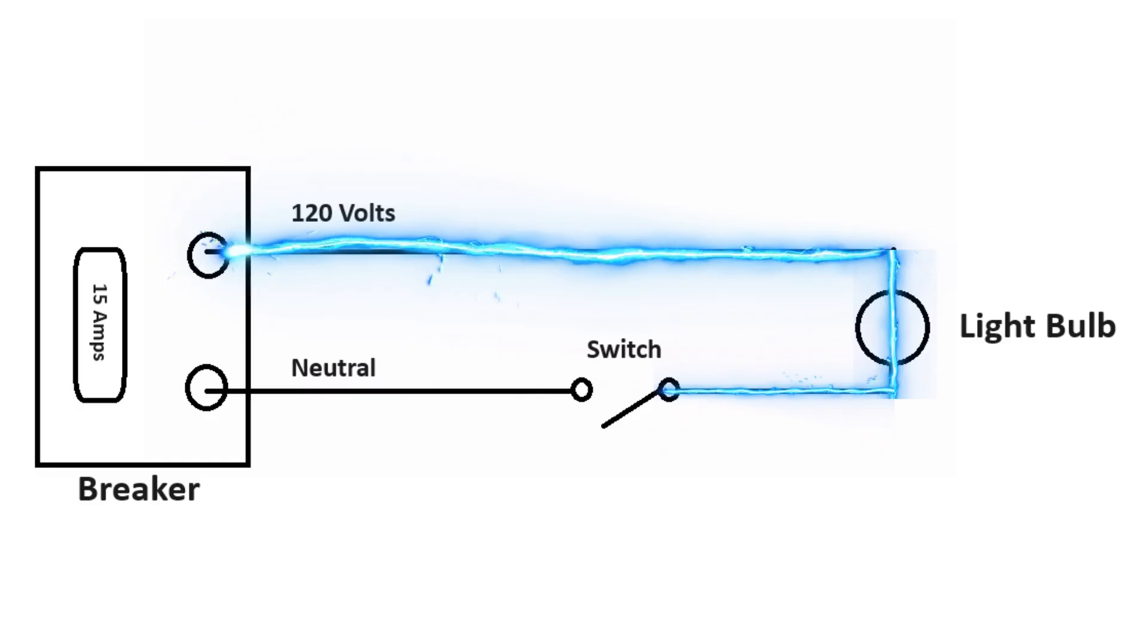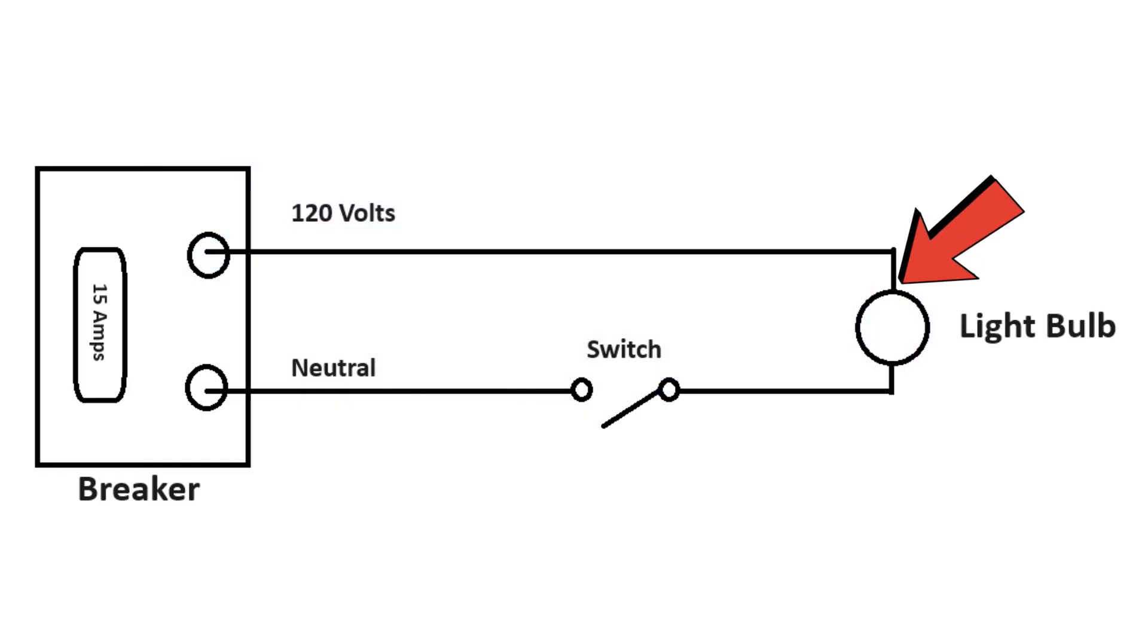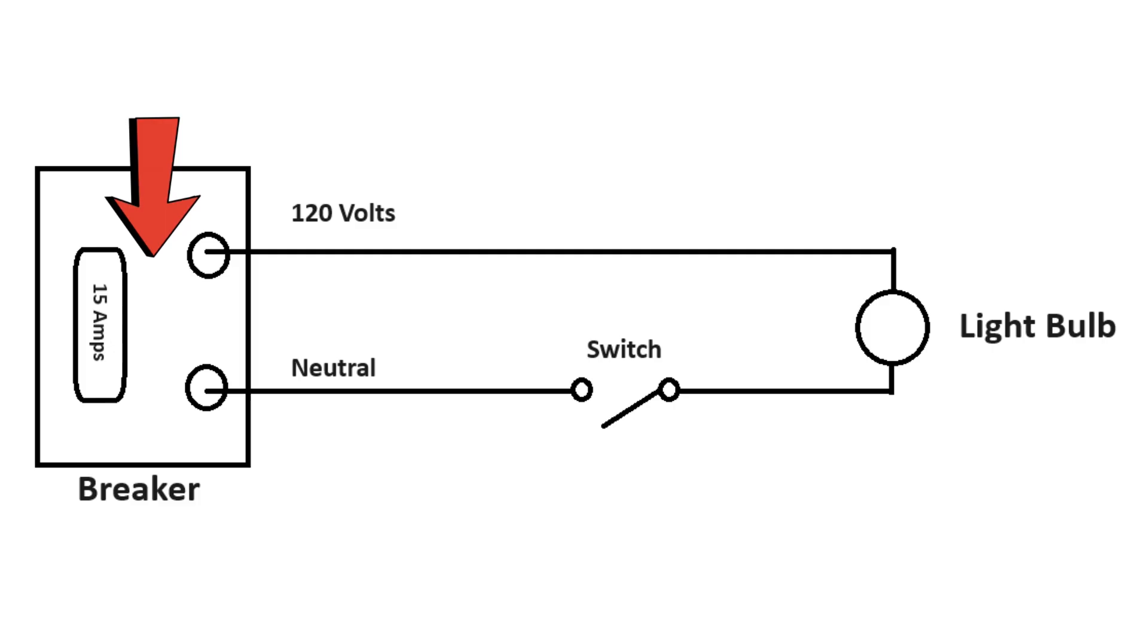The point here is that when you can start looking at a schematic in that way, you can start making key decisions on diagnostics and find key points where you can start performing your tests. And the schematic tells you what results you should get when you're performing that test. So if you were to test for power at a key point here and you don't have it, now you're starting to identify a problem. You might have a tripped breaker for example.